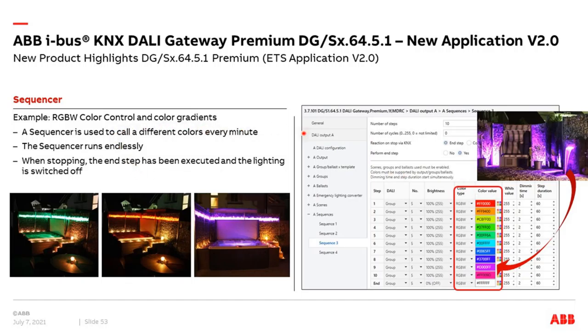Another sequencer example is color control with color gradients — for example in a spa with RGBW LED strips, where the color changes automatically from green to purple to blue to red. We create sequencer 3, select group 5 which is device type 8 RGBW, and click the color picker to enter the desired colors step by step: starting with red, then orange after one minute, then yellow, light green, dark green, blue, purple, and so on. With cycle count zero it runs endlessly, and when stopped it jumps to the end step and switches off all lights in group 5.